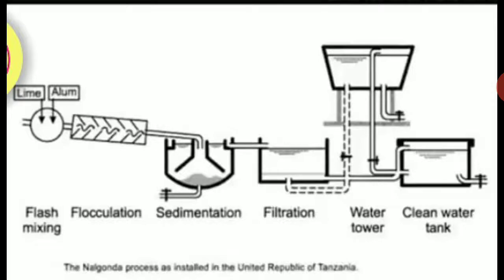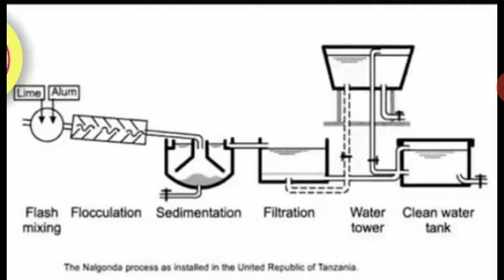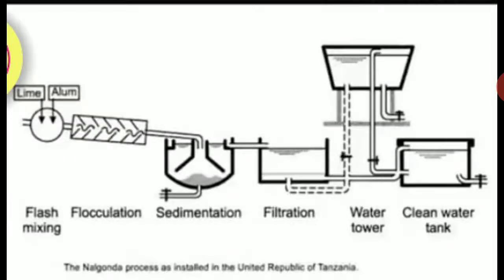In the sedimentation tank, the excess fluoride content settles down and is washed off through an outlet provided at the bottom. Only pure water is supplied to the filtration tank where the filtration process takes place. The filtered water is then pumped into the overhead tank for storage and directly supplied to the public. This is the Nalgonda process for defluoridation — the removal of excess fluoride.